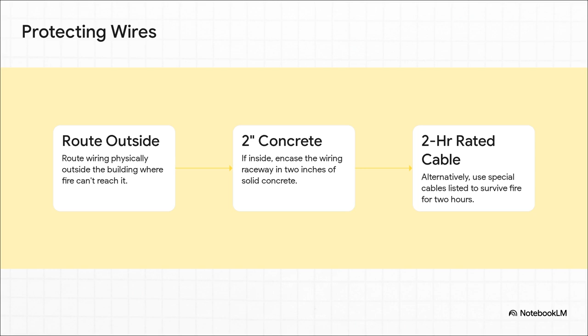The best option is to run the wires completely outside the building where the fire can't touch them. If they absolutely have to run inside, they get one of two treatments. Either they're literally encased in 2 solid inches of concrete, or they have to be these special, very expensive cables rated to withstand direct flame for 2 hours.